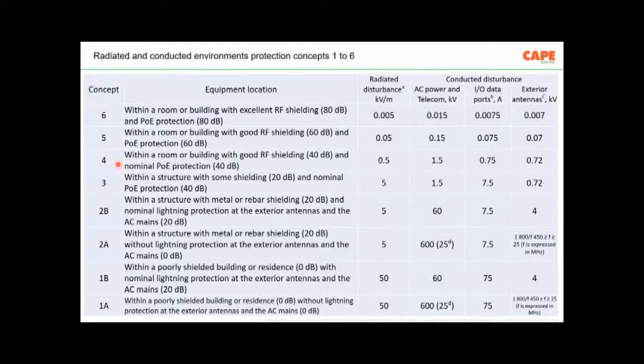2, 3, 4, and 5, they recommend this phenomenon or this kind of protection scenario for protection of buildings or electronic equipment in buildings, civilian facilities. So the protection concept 4 or 3 is actually possible if we design and install our electrical and electronic installation, or if we design our building with an aim to protect the electronics from such disasters of EMI.